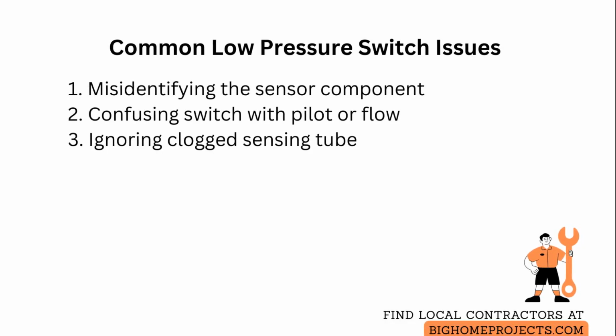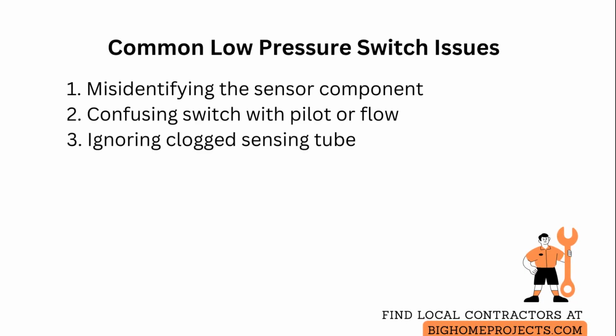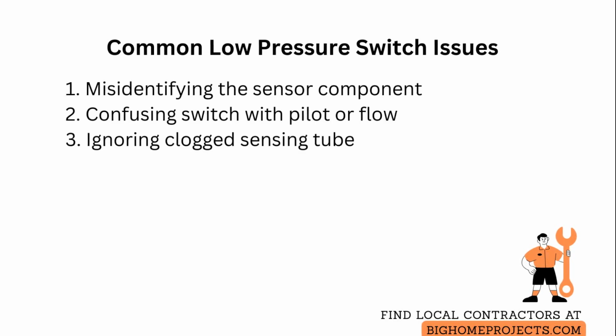A frequent oversight is neglecting the sensing tube or port, which can be clogged with condensate or debris and will mimic switch failure. Clear or replace the tube and retest the switch before ordering parts.